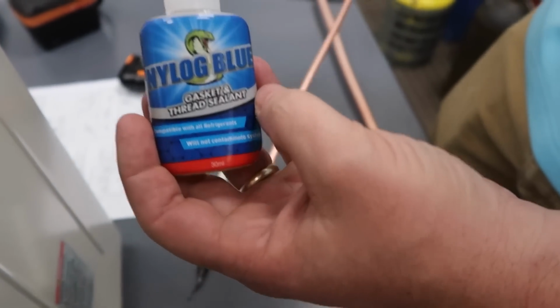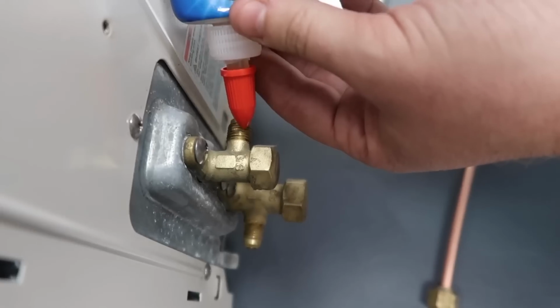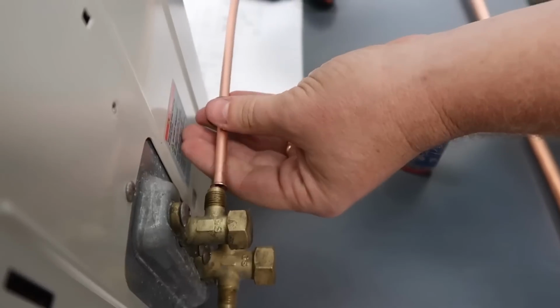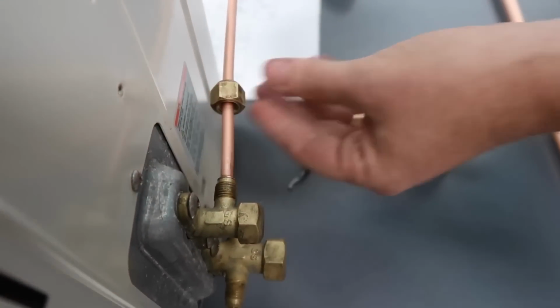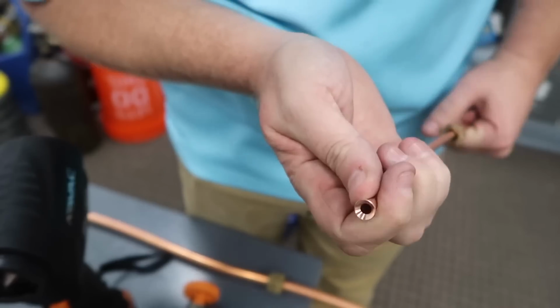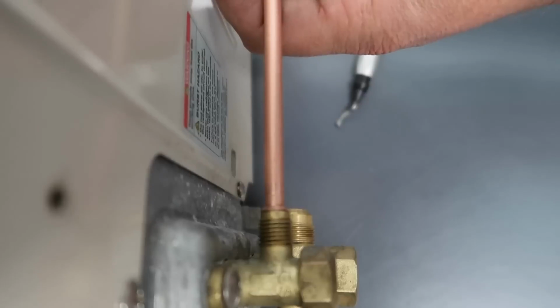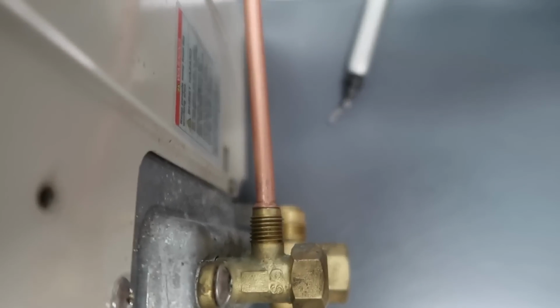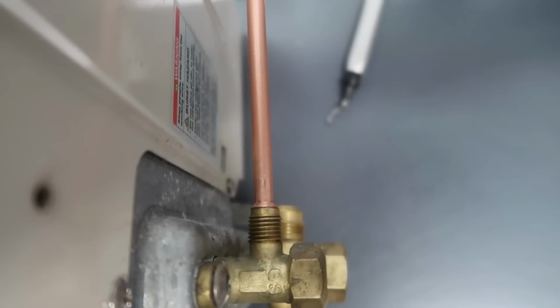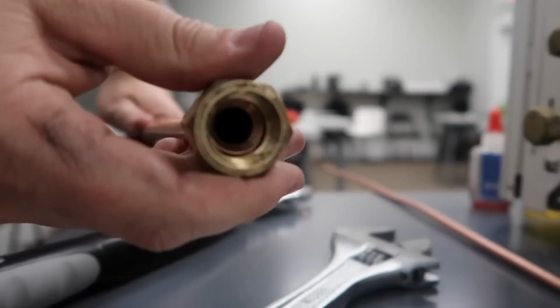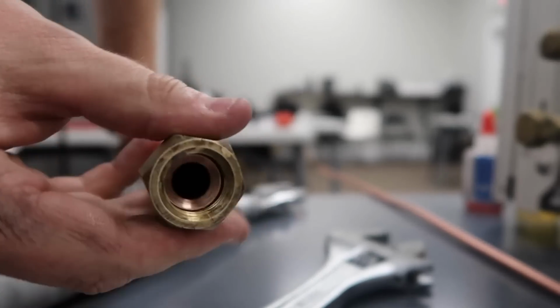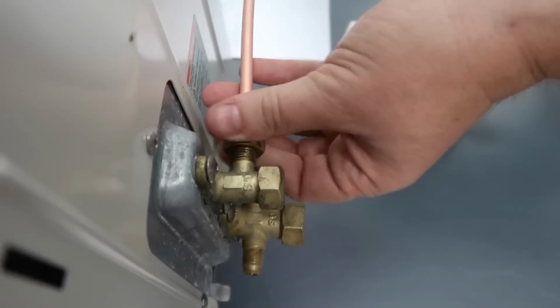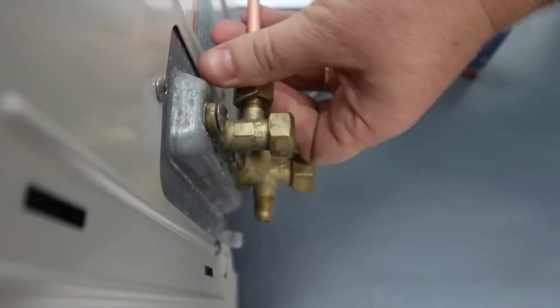Yeah, I mean, we're a little bit more heavy with the nylog in general, but to your point, if you follow the ways the manufacturer tells you to do it, you're going to be safe. The biggest thing is the obvious best practices, like making sure you don't have scuffs on the flare face, making sure the flare is the right size, and mating it up and checking that it lines up. Is everything the way it's supposed to be? Using the manufacturer's flare nut. That's actually a really big one that I often forget to mention. So thank you for mentioning that.